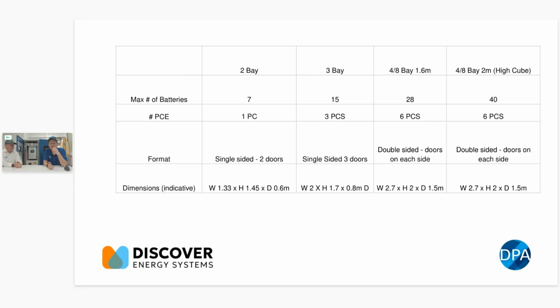But with the Trinix, or typically you're going to put a Trinix or the bigger Scion, they take up a bit more depth, so you can only have one per bay. These can be done single phase or 3-phase, depending on the topology. We're doing one at the moment which is 60 kilowatts, 3-phase, with two 10-kilowatt Victron inverters on each phase.